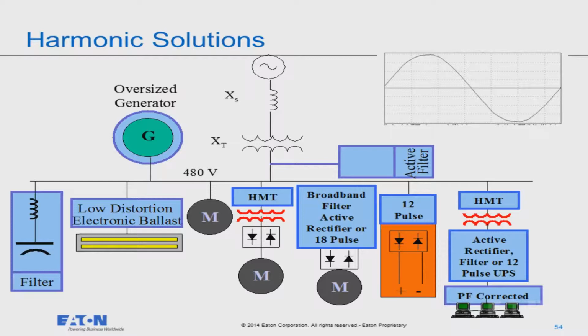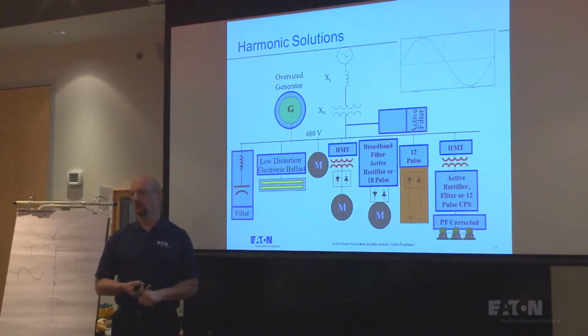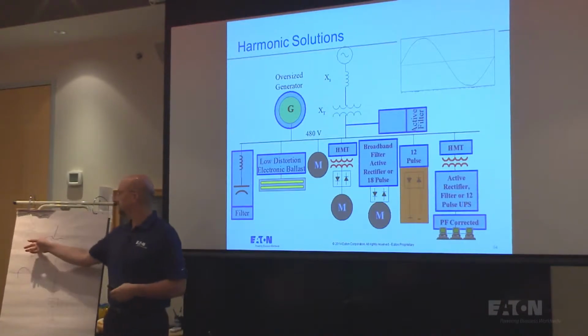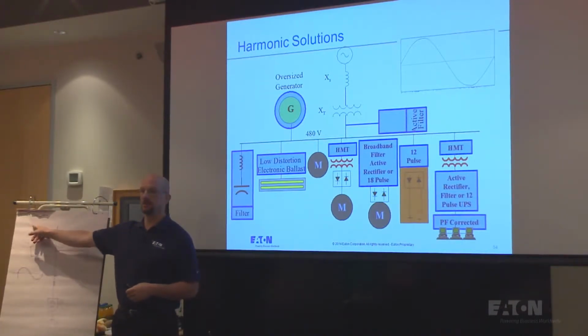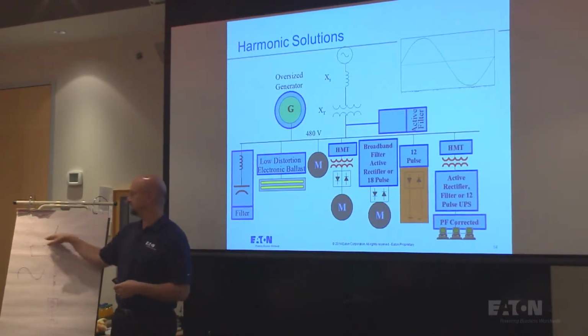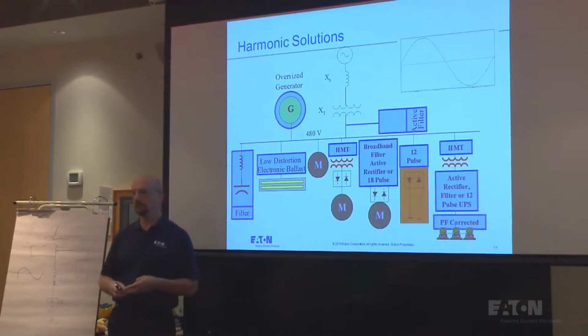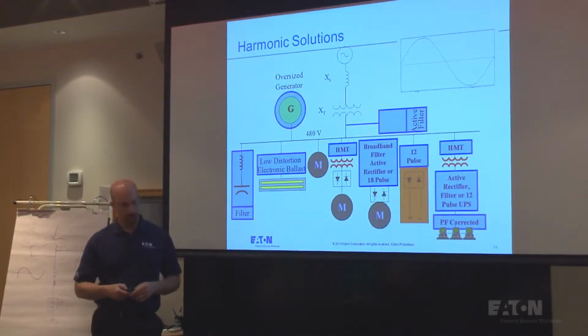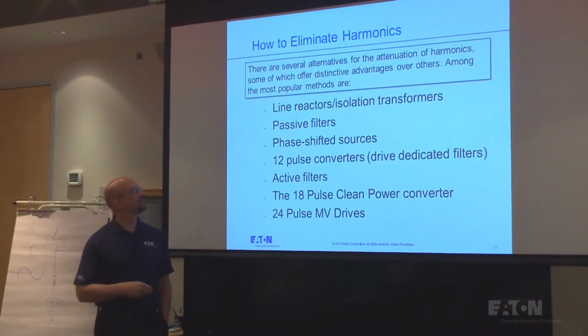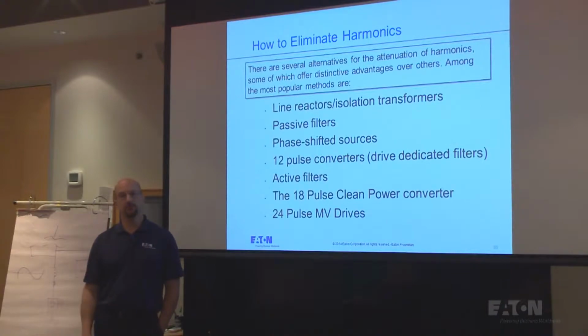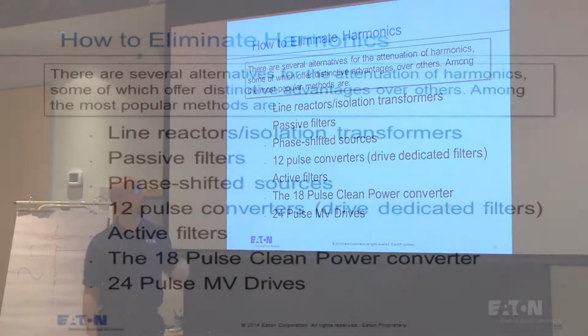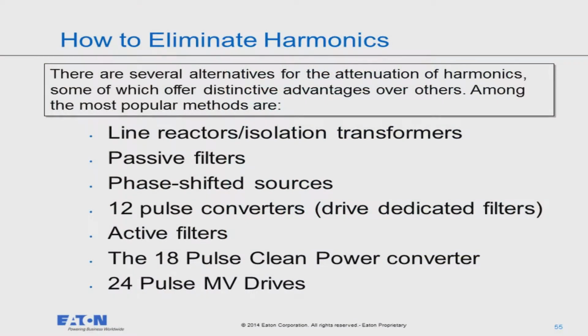What happens if I really need a 1,000 kilowatt generator, but I put in a 2,000 kilowatt generator? What have I effectively done? Reduced the impedance. So over here where my impedance was 18%, now on the nominal basis compared to what it should be, it's 9%. So now my impedance difference isn't as big of a deal. Yeah, but it cost me a lot more money to do it, right? So here are some of the typical solutions for drives, and we'll talk a little bit about each one of these.